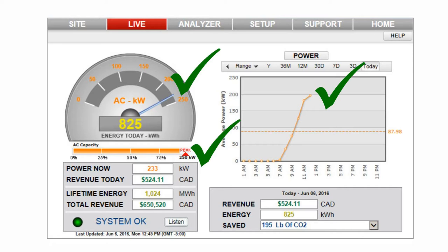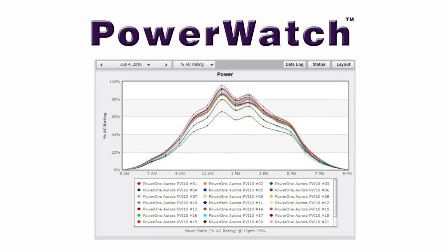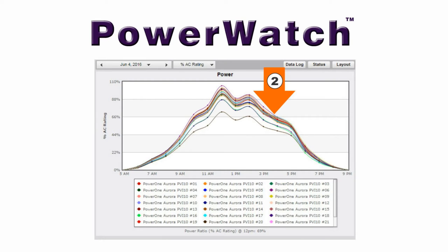Yet there's a problem that basic monitoring systems would allow to go undetected. SolarView has a powerful tool accessible from the analyzer called PowerWatch that quickly identifies hard-to-find problems like bad strings, blown fuses, shutdown equipment, and faulty inverters. PowerWatch continuously compares all inverters and checks differences between them under the same solar conditions. PowerWatch displays a graph of daily output power of all inverters, which shows visually which are underperforming. Normally, only small variations in output would be expected.